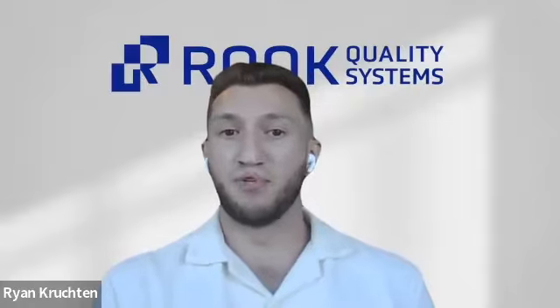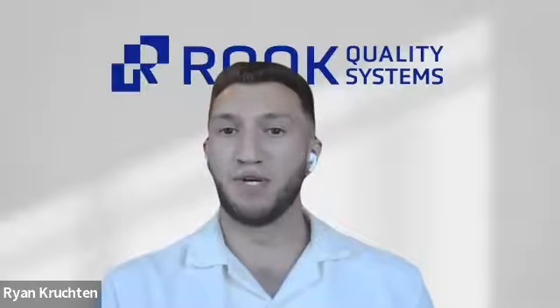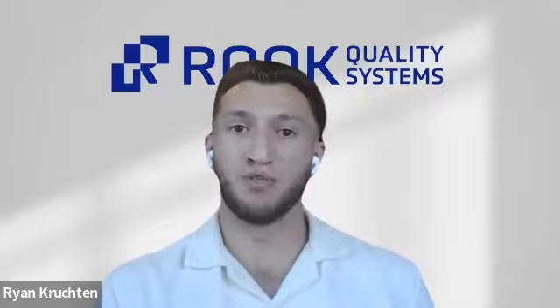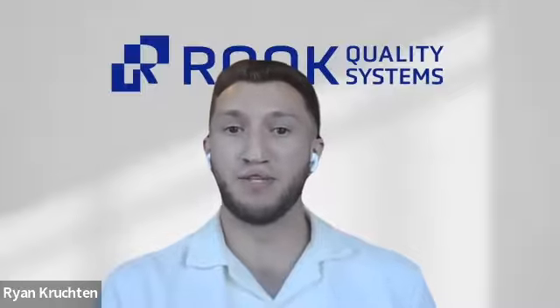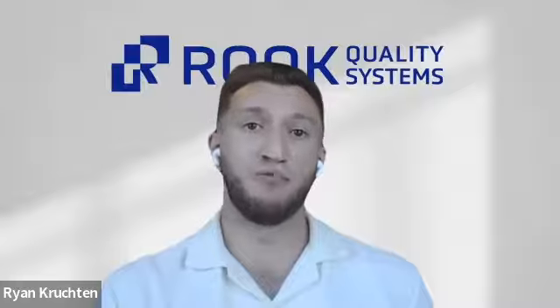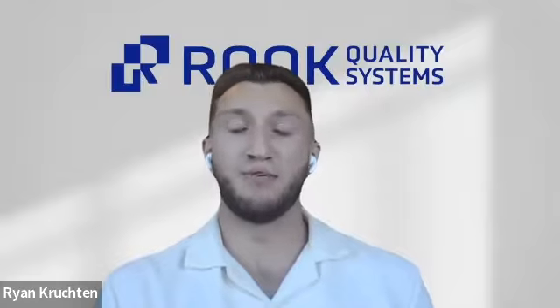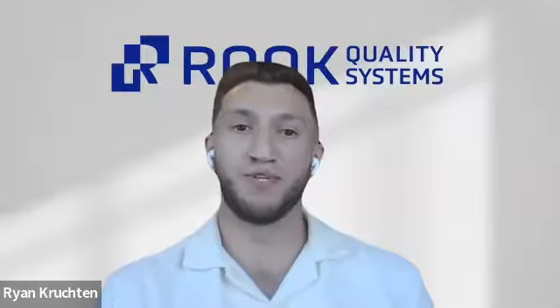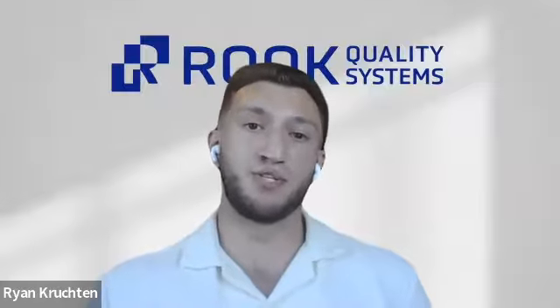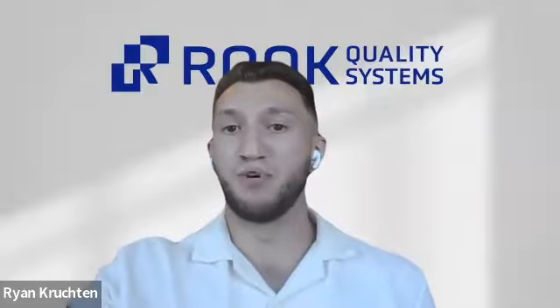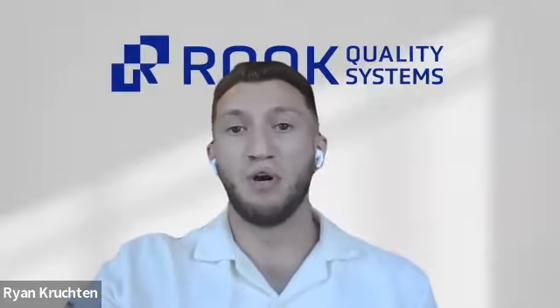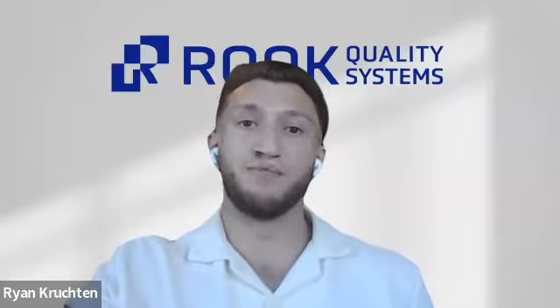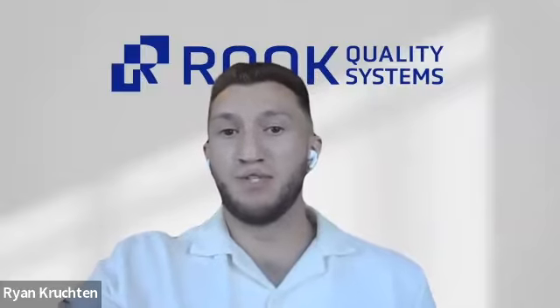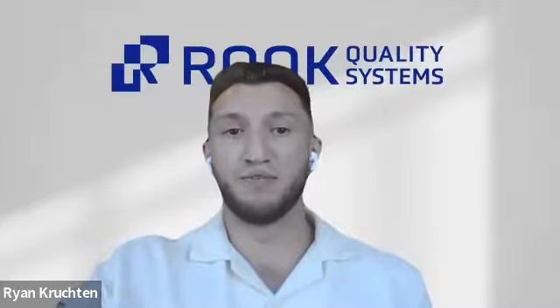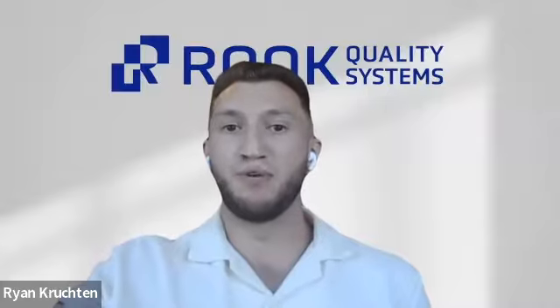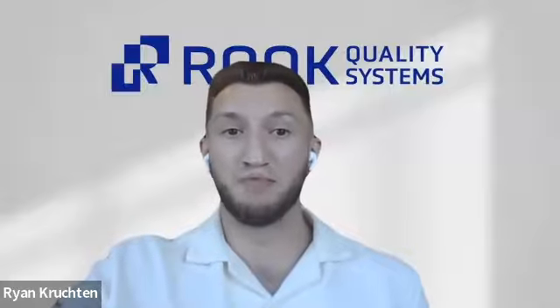So this starts with a risk-based approach, just like everything else. We need to look at cybersecurity, not just through the lens of potential attack vectors, but also through clinical impact. So what could happen if a vulnerability is exploited? This question is key for understanding in our cybersecurity risk assessment how risks translate to clinical impact, not just technical inconveniences. So could it lead to something like a delayed therapy, a loss of function, or maybe an incorrect dosing or device output? Those questions have to be answered early, and the mitigations should be built into your design rather than patched in later, if you care about saving time and money in development.